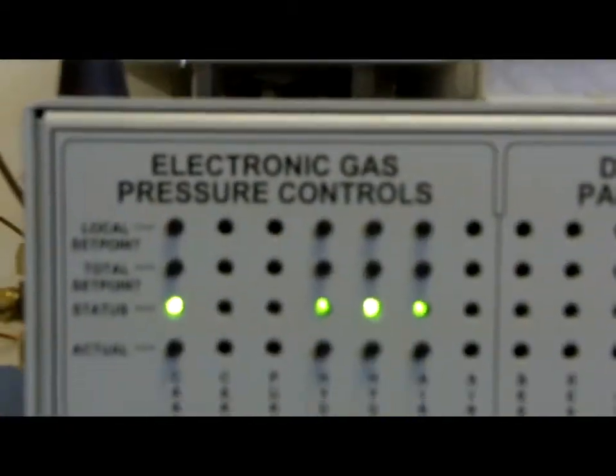The mud logger GC is configured with an internal air compressor and can use hydrogen as both makeup gas and carrier gas for FID detectors.